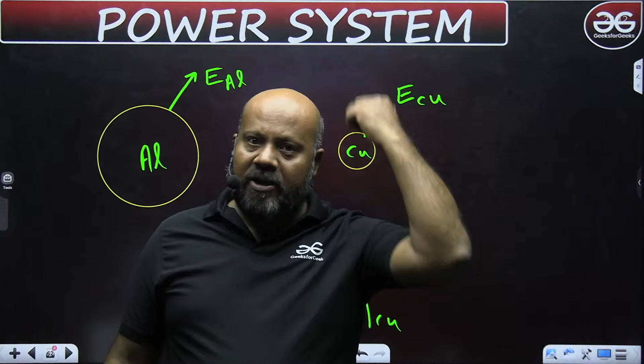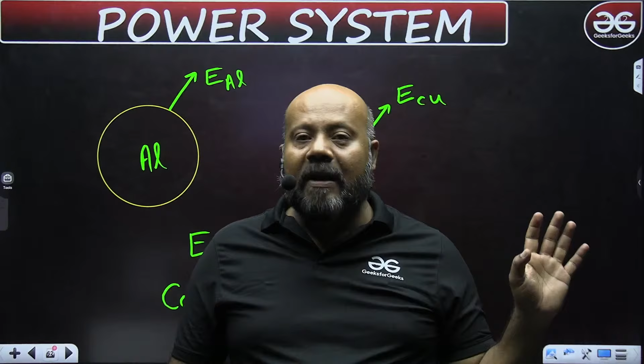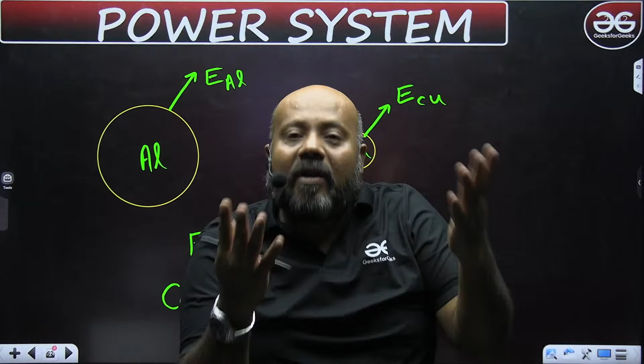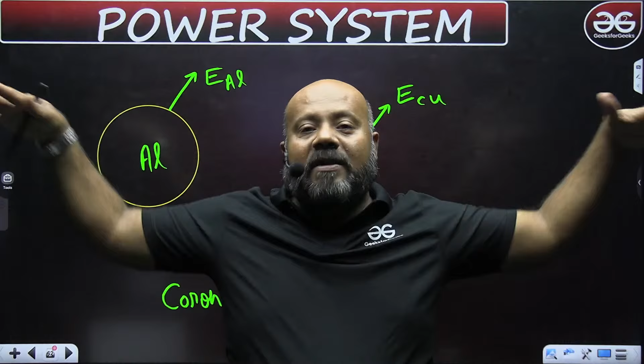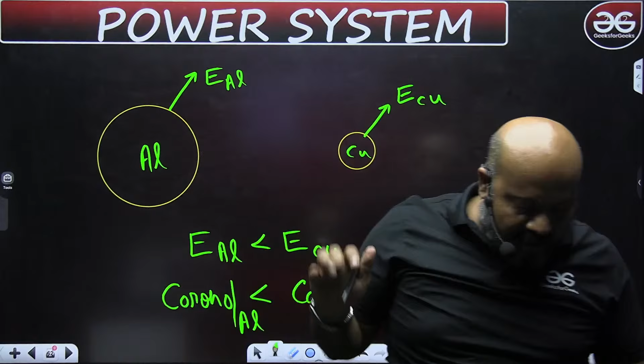There are some other reasons, as Ashish has mentioned: cost is one reason, and availability—aluminum is available in abundance—is another. Weight to density ratio is one reason too: the weight of aluminum relative to its density is comparatively very less. So if the weight is less, the sag of the conductor is less. If the sag is less, the required ground clearance is more, so the height of the tower is less. Overall, you can say there is a saving in the system. Everybody is getting this? Say yes or no.